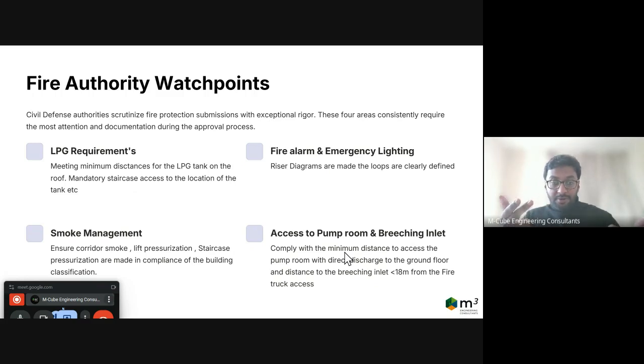Again, related to the LPG tank, you need to ensure that the staircase has direct access. You cannot place an LPG tank on the top roof where you don't have direct access from the staircase. This is something you need to look for at the initial design stage, because currently on roof floors you have a lot of swimming pools and infinity pools coming in, which limits us as MEP engineers in placing our equipment on the roof. Ultimately, as engineers we need to ensure we are complying with the authority requirements. So this is something to keep in mind at the initial stage of design itself.